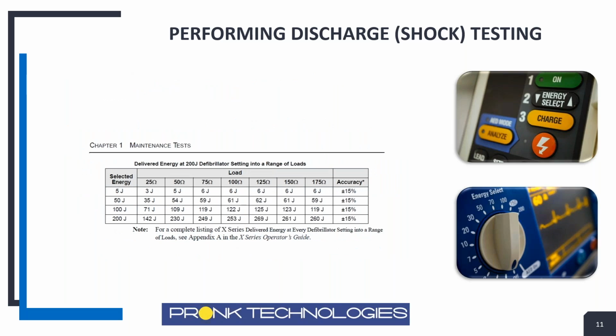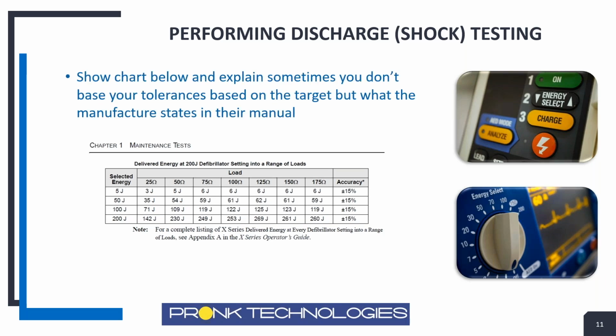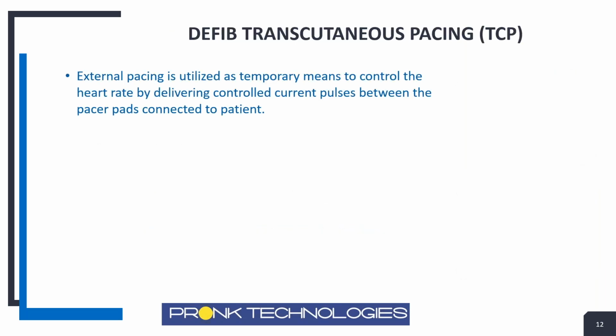So here's an example of what the chart looks like across different impedances. This chart tells you, for X setting of energy across different impedances, the expected energy to be delivered varies. It's not the same. It should all be within specification, but they're not the same depending on what that impedance is. So the defib does a great job, but you have to understand that the results could vary depending on what that impedance is.